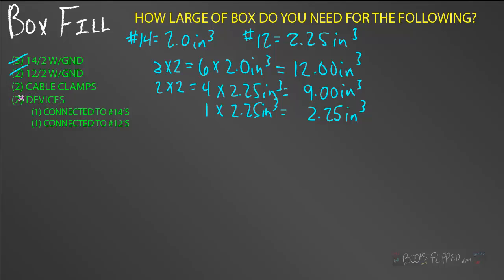Let's move on to cable clamps. Remember, it's just like the ground. All the cable clamps count as one conductor of the largest size. So, let's just duplicate this formula right here. One times two point two five equals two point two five cubic inches. Now, I can cross that one off.